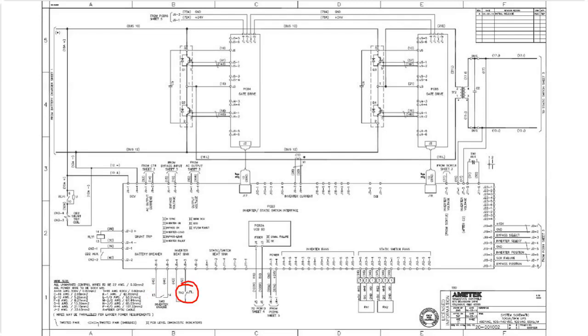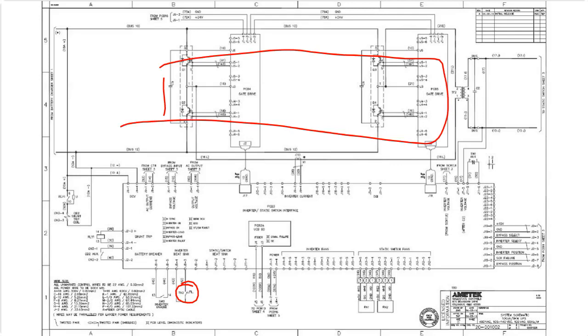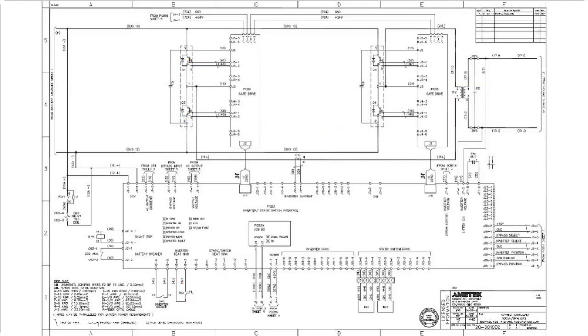And TH2 is, once again, a thermostat that's attached to the bridge that these IGBTs are mounted to. If that goes above 90 degrees C, then that thermostat closes and it will shut down the inverter. Actually, I think it transfers to bypass. I'd have to check on that. I can't remember on the DPP. But it definitely takes the load off of the inverter so it can cool down.